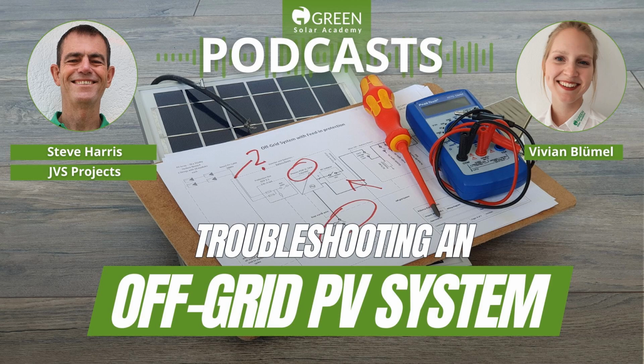So if we look at that, the most common problem is the customer has either overloaded it or used it when the batteries are very low, because they don't understand how much load you're taking off it on a cloudy day, for instance. You'll find predominantly with us it's an AC system—we've got inverters, we have very few pure DC systems out there, just the nature of our market. So we have a lot of inverters that switch off.